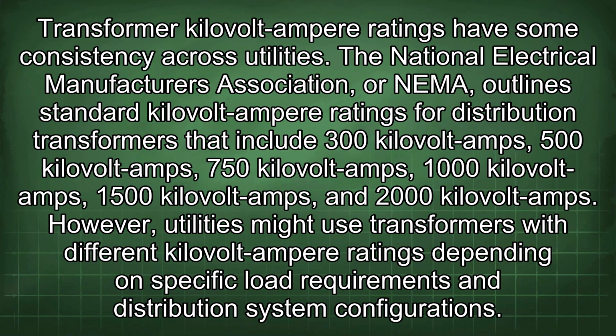Transformer kilovolt-ampere ratings have some consistency across utilities. The National Electrical Manufacturers Association, or NEMA, outlines standard kilovolt-ampere ratings for distribution transformers that include 300 kVA, 500 kVA, 750 kVA, 1000 kVA, 1500 kVA, and 2000 kVA. However, utilities might use transformers with different kilovolt-ampere ratings depending on specific load requirements and distribution system configurations.